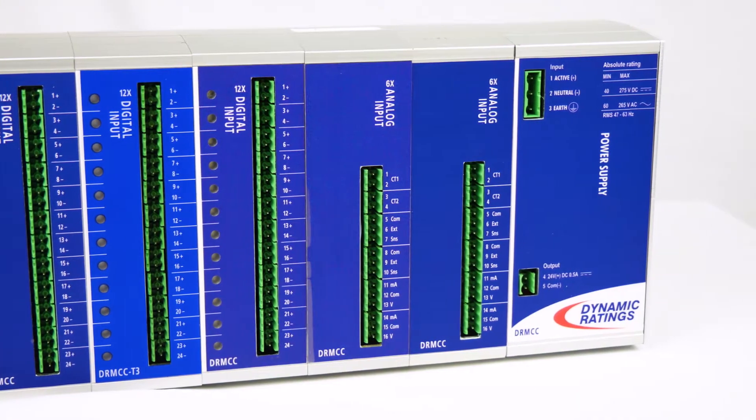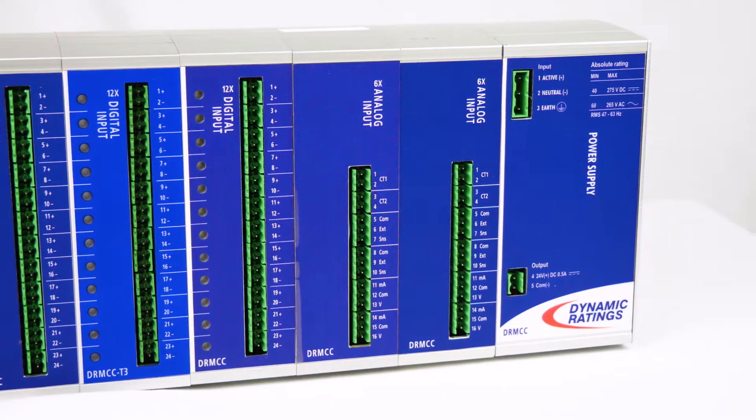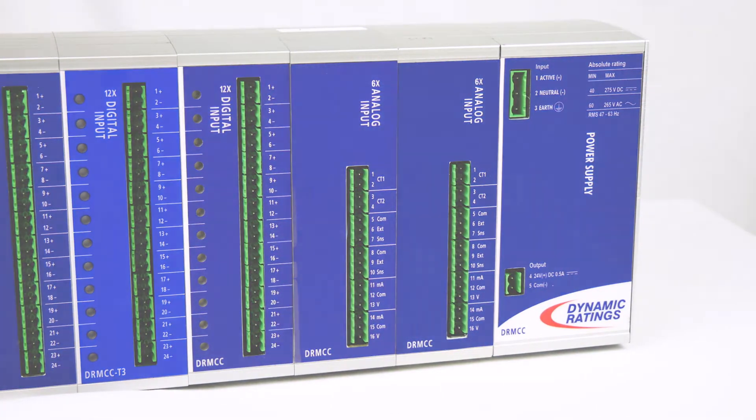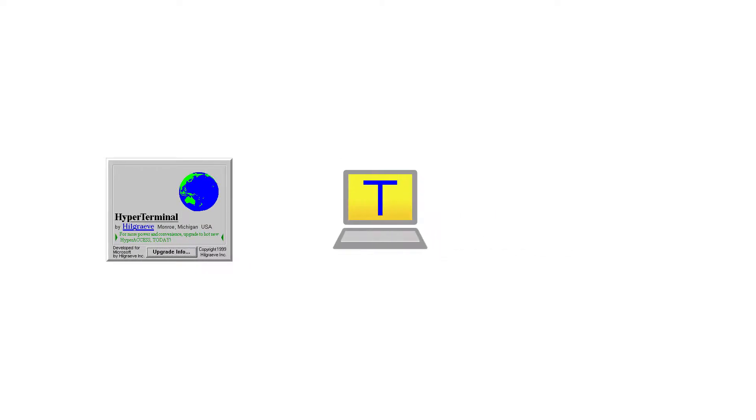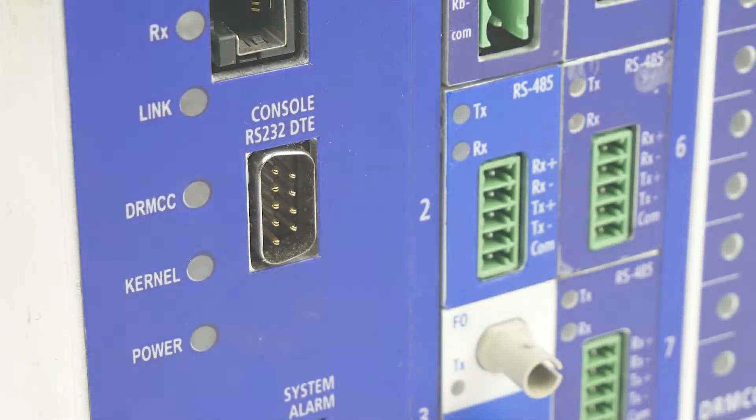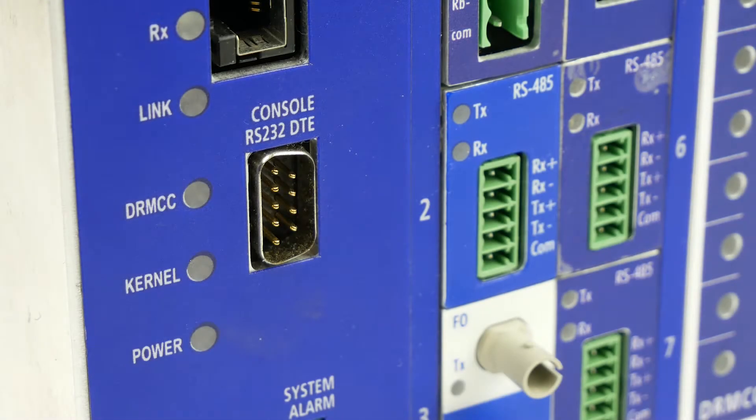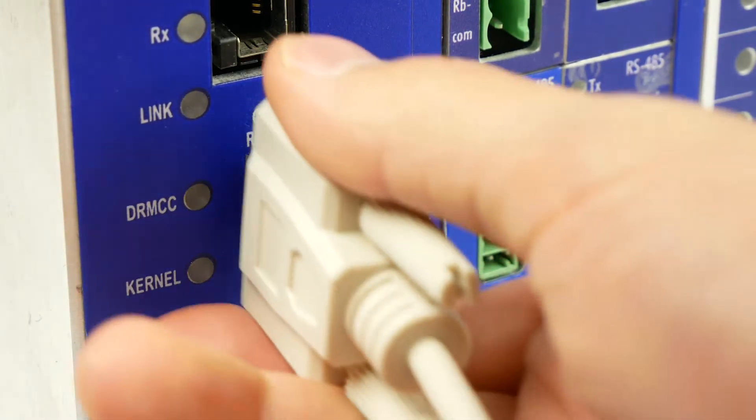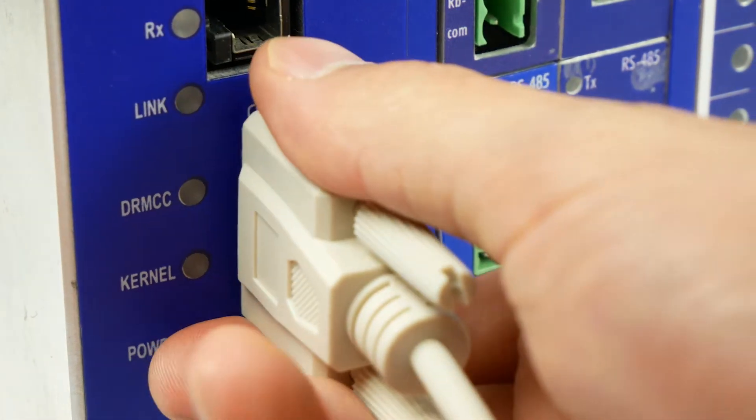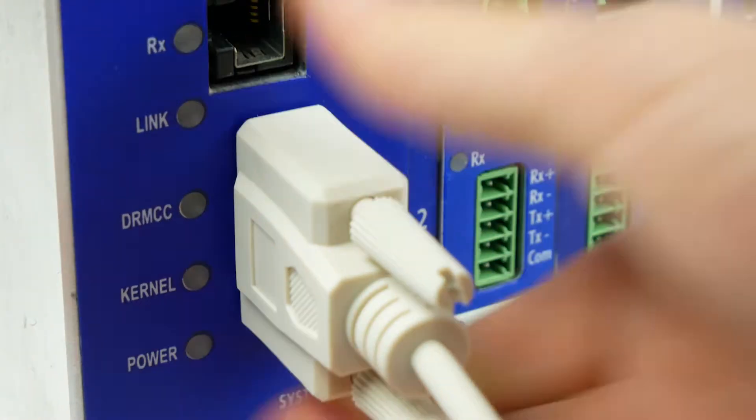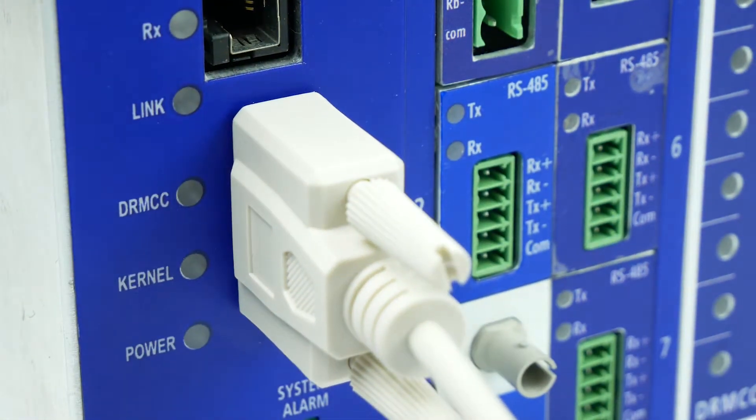In order to connect to the T3, you will need a terminal application with the ability to transfer files like HyperTerminal or TeraTerm, or an FTP software such as WinSCP. To transfer files serially, you'll need to connect using a null modem cable to the console RS-232 port on the T3 CPU located on the far left side of the unit.